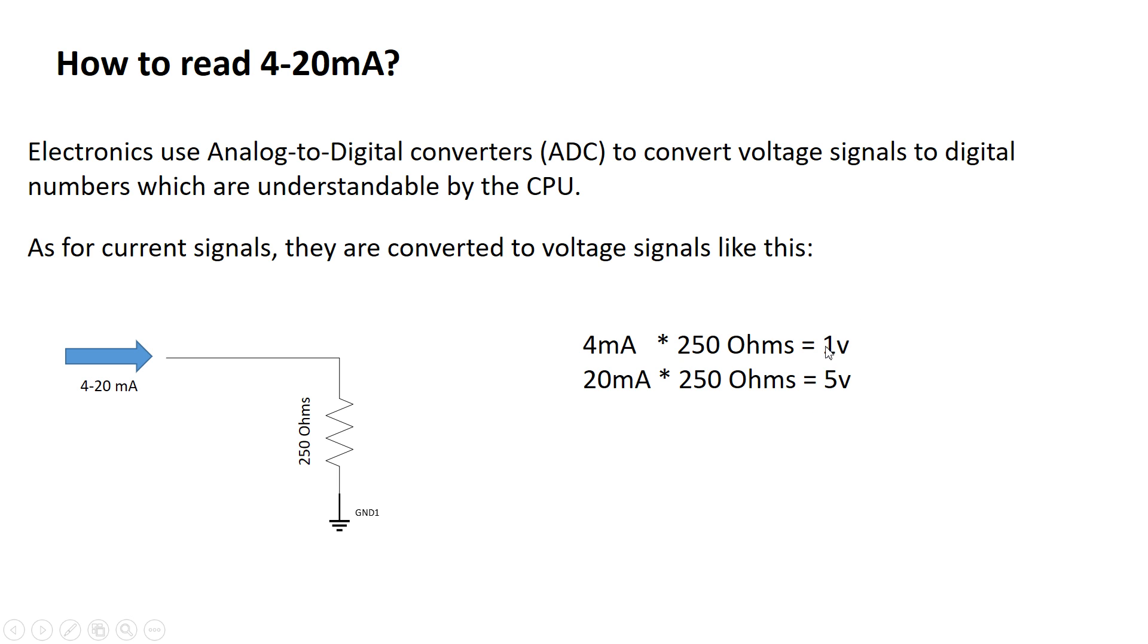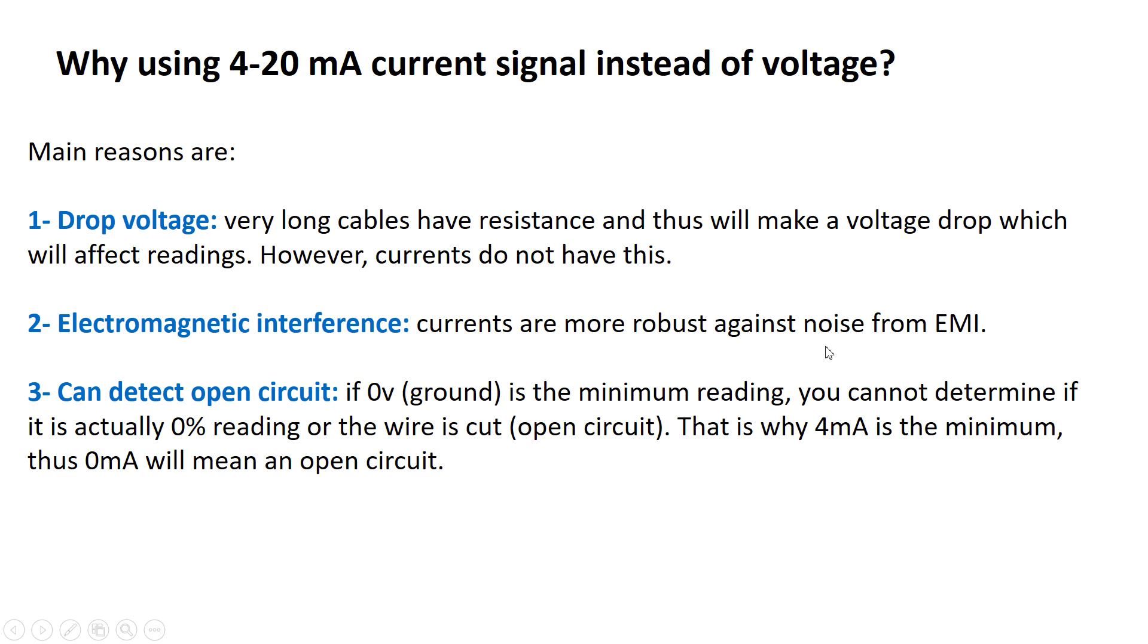Now why do we use the 4 to 20 milliamp current signal instead of voltage? The main reasons are: first, voltage drop. For very long cables, which are the standard in industry or any plant, these have resistances in them and this will make a voltage drop in the wire before the signal goes into the measuring device. It will be changed. However, currents do not have this issue.